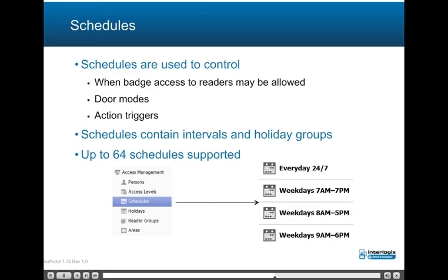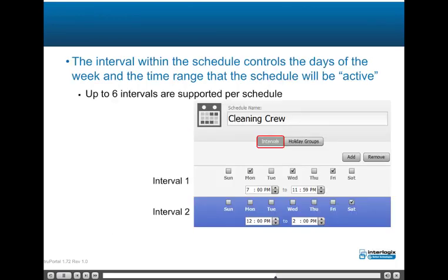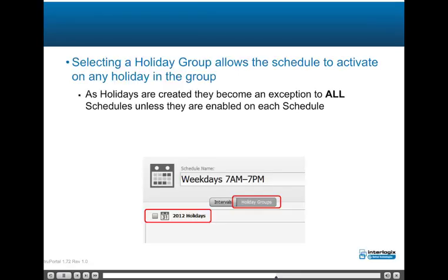Schedules are used to control when badge access to readers may be allowed, door modes, and action triggers. Schedules contain intervals and holiday groups. The system allows up to 64 schedules. The interval within the schedule controls the days of the week and the time range that the schedule will be active, with up to 6 intervals supported per schedule. Selecting a holiday group as part of the schedule allows the schedule to activate on any holiday defined in the group. Note that as holidays are created they become an exception to all schedules unless they are enabled on each schedule.